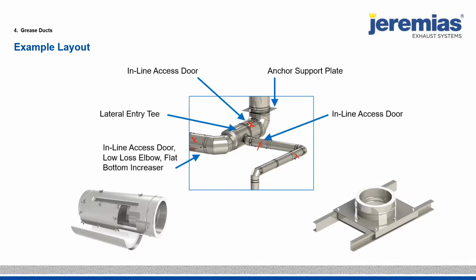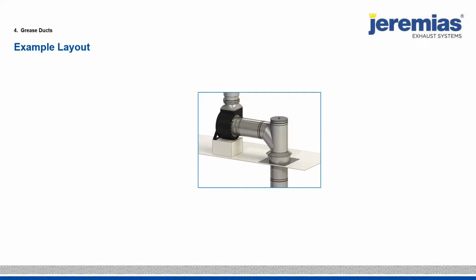Hey, Larry, real quick question for you. Is there a code or a rule of thumb of the distance between inline access doors? Yeah, we follow the local codes. NFPA 96 states have 12 feet spacing, and then the IMC has 20-foot spacing, and also at every change of direction. So thank you for bringing that up. We do follow the local codes as required for access.